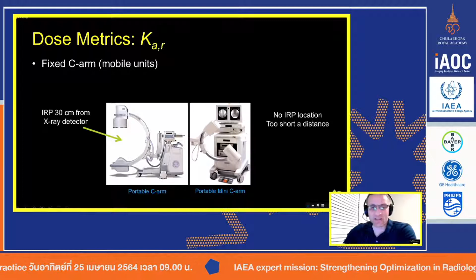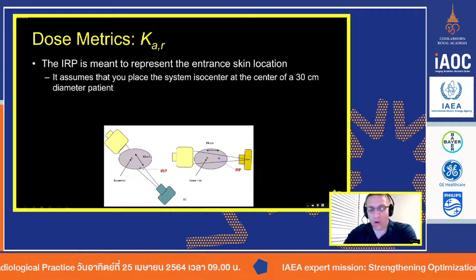So as I mentioned, why is the IRP, the international reference point, at 15 centimeters? Well, if you have a typical patient that is roughly 30 centimeters thick or in diameter, as long as the isocenter is dead center to the patient, then that international reference point is going to give you a pretty good approximation to the entrance skin dose. So the value you see on the monitor gives you a real-time value of how much radiation is exposing the skin. Now, the problem with that is we're not all exactly 30 centimeters thick, and we don't always have the isocenter exactly in the center of the patient.